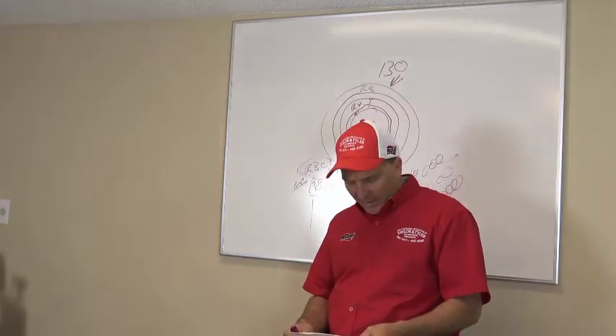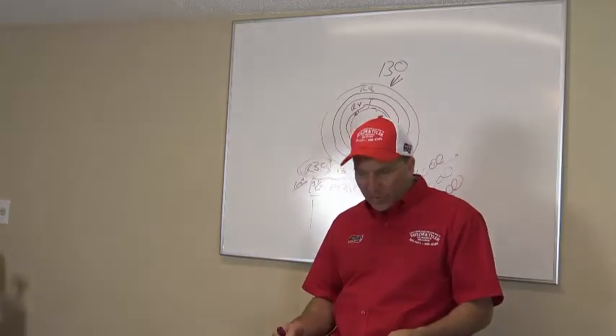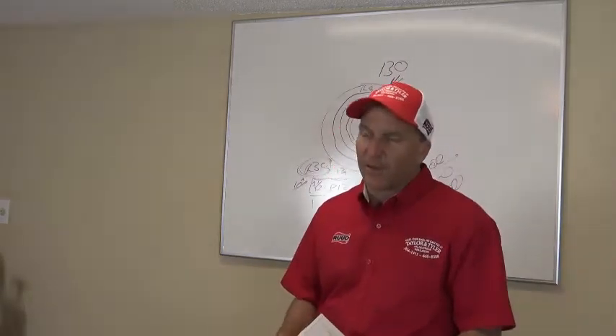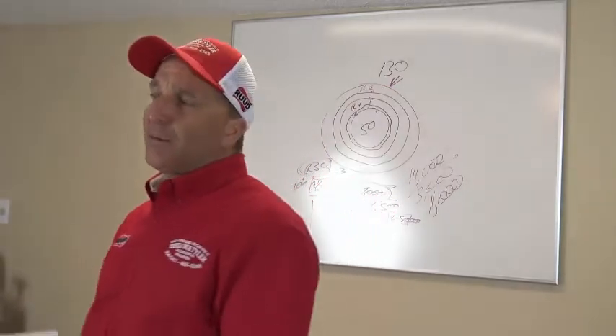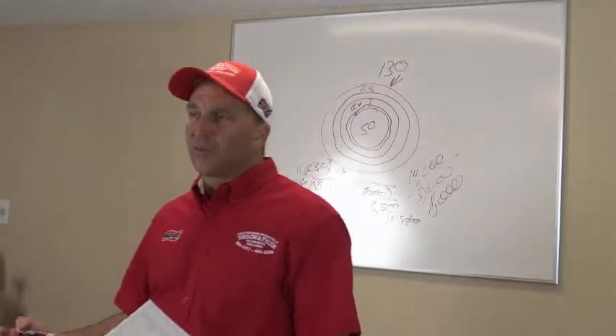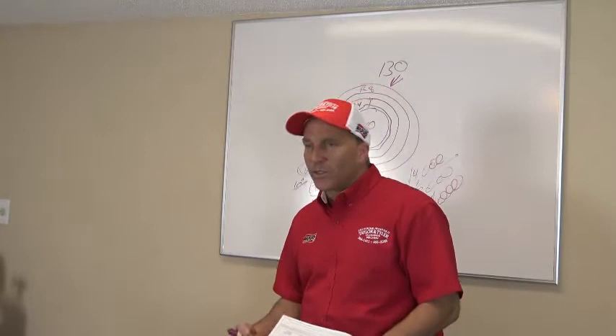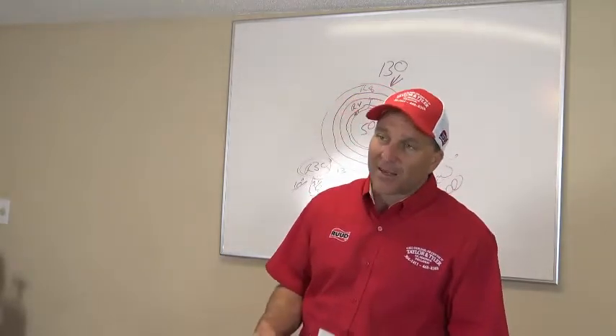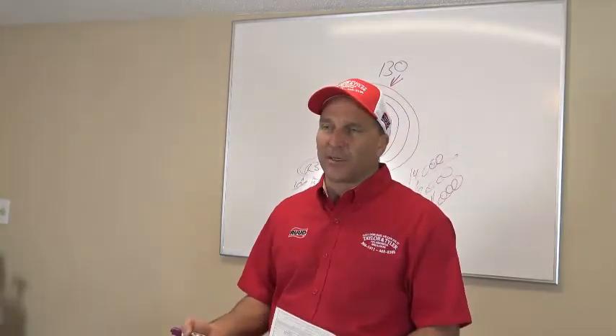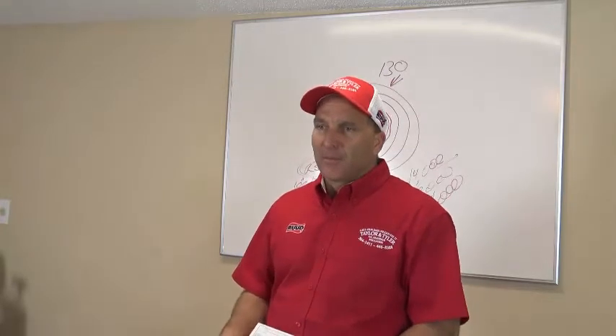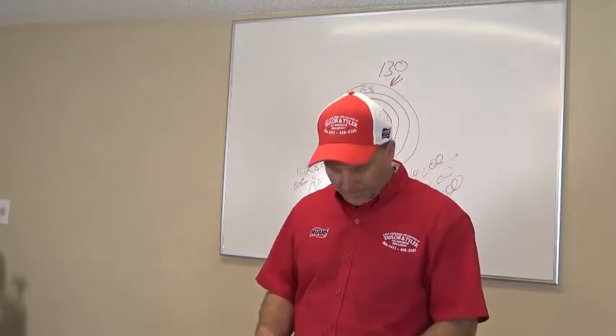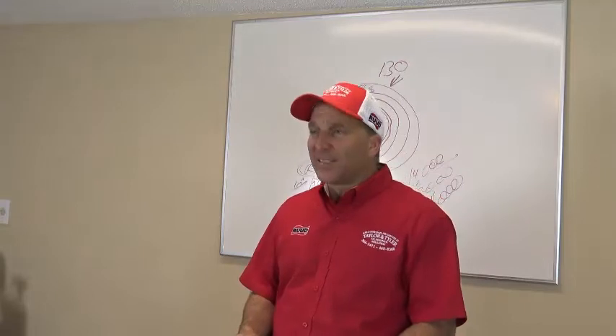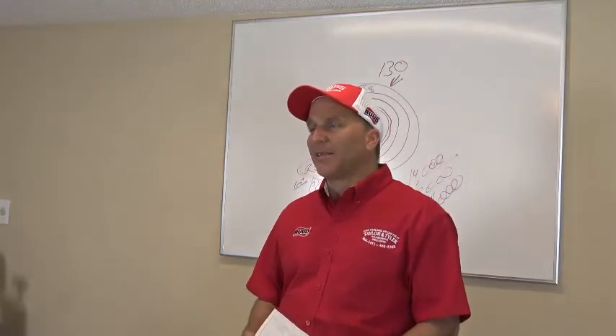Float switches. I need to know if you have any float switches on your system or if they're broken, if the connections are making. Most of the time, you've got to just look at the system and see that the float switch is there and if it's actually hooked up. A lot of times I see a float switch there, but it's actually not even hooked up. Make sure they're wired in correctly, guys. Okay? If it doesn't have a float switch on your system, how do you sell it?